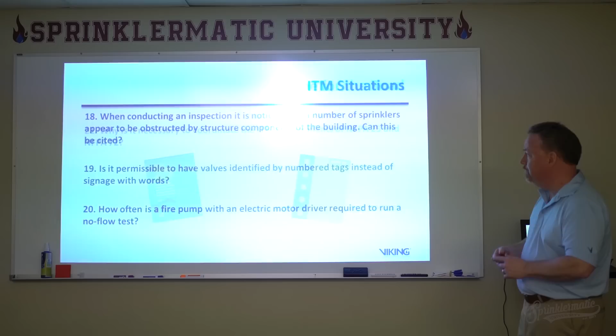Because they're different, yet the two systems work together. We have pre-action systems and deluge systems that rely on the detection system to operate. And we have other situations where fire alarm systems installed in our buildings monitor the condition of operations within our system, like the position of valves, the status of the fire pump, and water flow in the system.